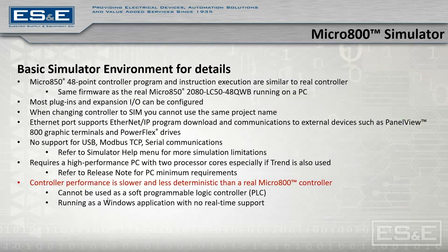On the other hand, this is not a replacement for your controller. It's not to be used as a soft PLC. The reason why is that it is much slower. I don't know if you saw that, but it actually took a second or two for the inputs to come on. And it's not deterministic, just meaning that I could click the input, it may come on in 1 second, it may come on in 2 seconds, it may be 50 milliseconds. So it's not really deterministic. You wouldn't really want to use it in a production environment where you are controlling from your PC. Great for testing, but probably not a good idea for actual control.